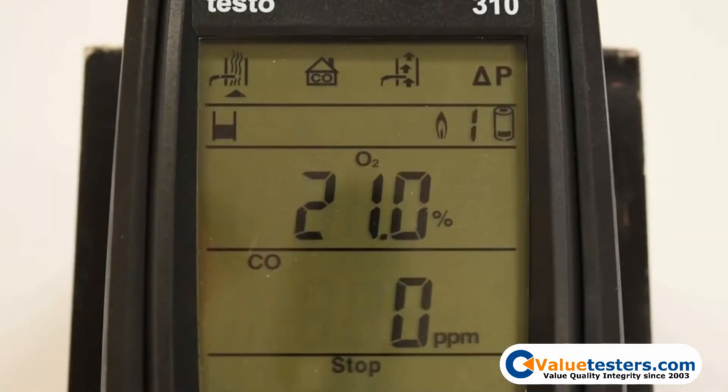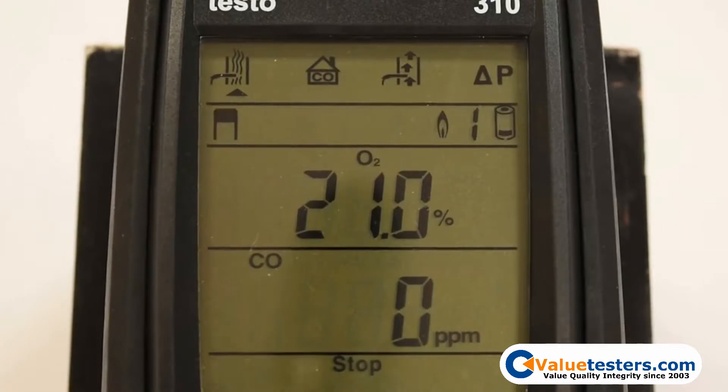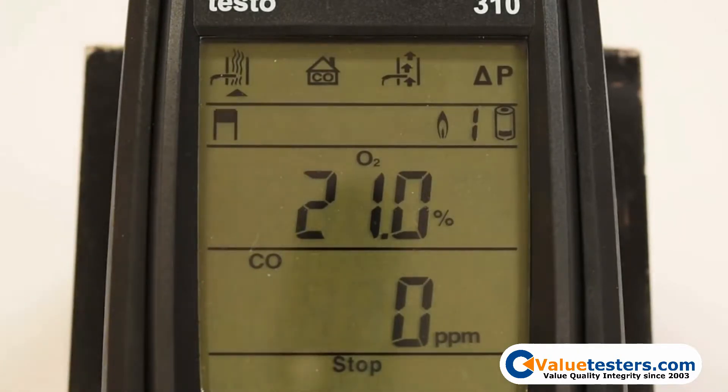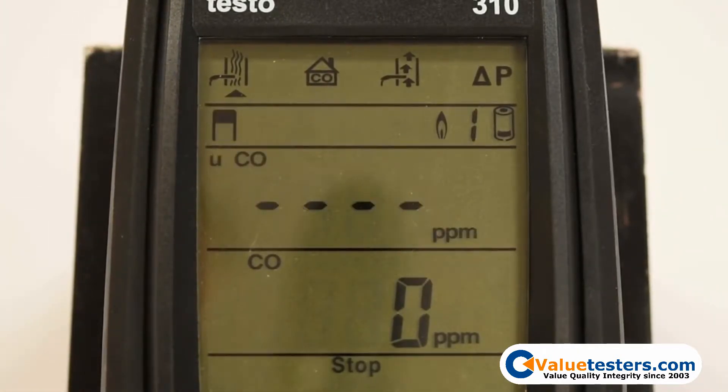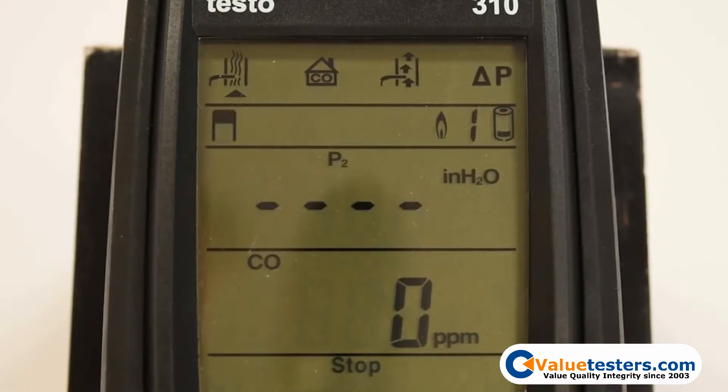When selecting the flue gas test, the measurement values are displayed on two lines. However, additional measurement values are calculated simultaneously and can be viewed by the up and down arrows.